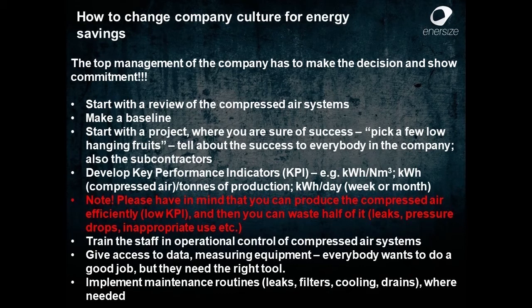We need the performance indicators. And remember, when we are dealing with compressed air, we may need more than one performance indicator. We can actually produce compressed air in a very efficient way, and we will see that reflected in kilowatt hour per normal cubic meter. But another performance indicator could also be electricity going to compressed air per ton of production per week or per month. And the reason for that is the red text here.